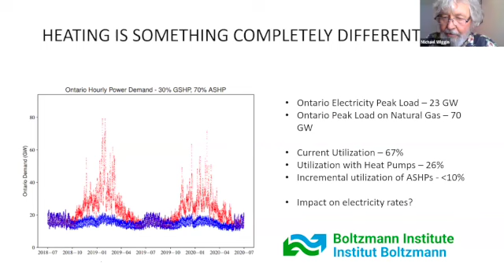But if you look at the heating by itself, it's even worse than that. If you're not familiar with load duration curves, basically, if you go back to a load curve like I was showing you before for heating, divide it up into 1 hour sectors and rank it from highest to lowest, you'll get a curve that looks like the blue one there. So the peak, the 100% of peak load, is very, very short duration, but you've got to meet it. You can't say, oh, we're not going to provide heating today, it's too high. Doesn't work. And overall, over the year, the utilization is only about 25% of that peak capacity.